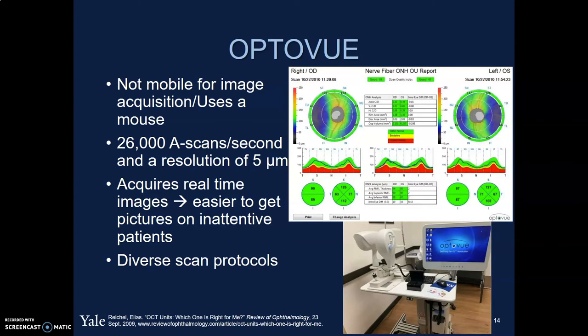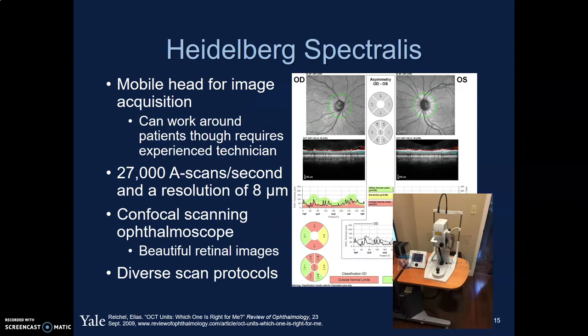Next, the OptoVue. Also not mobile, still reliant on patients. It does about 26,000 scans per second and has a resolution of about 5 microns. It requires real-time images, which makes it a little bit easier to get pictures on inattentive patients. And finally, there's the Heidelberg Spectralis, which has a mobile head for image acquisition, so you can move the head around to get around various obstacles — like a large exotropia or a scar on the cornea — to get better image quality. It requires a little more experience to use, but is less patient-reliant. It does about 27,000 scans per second with a resolution of about 8 microns.